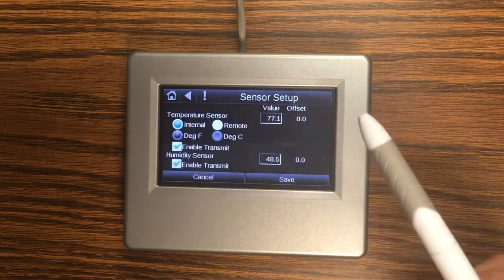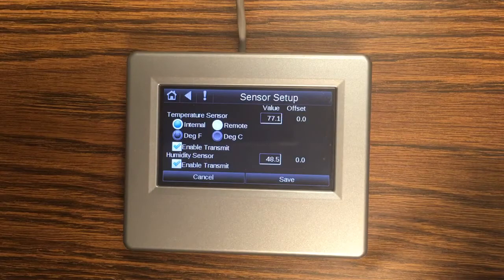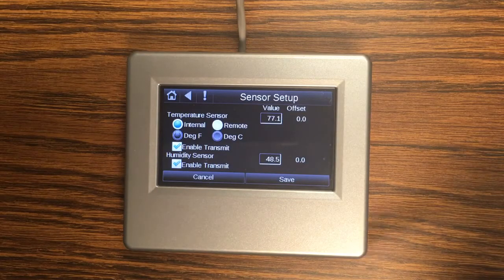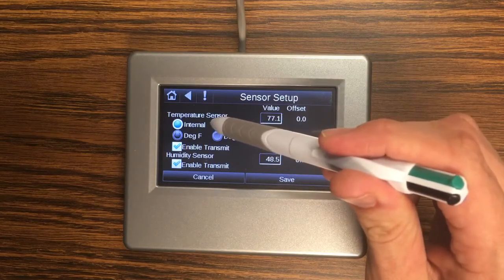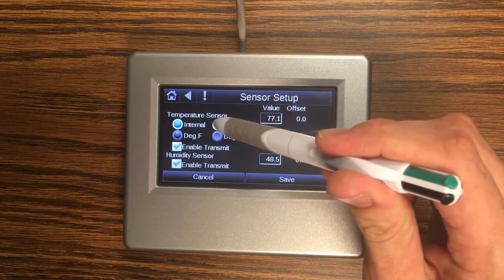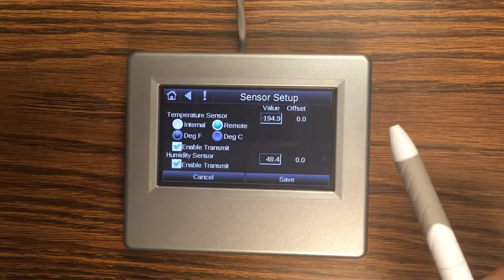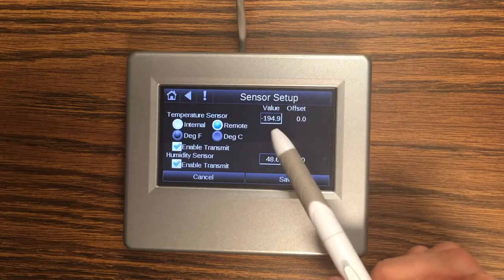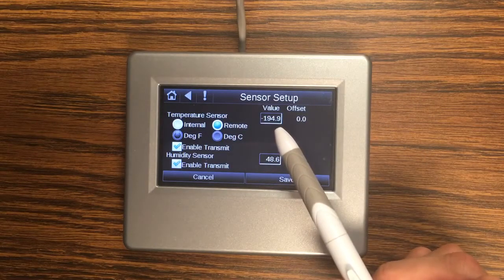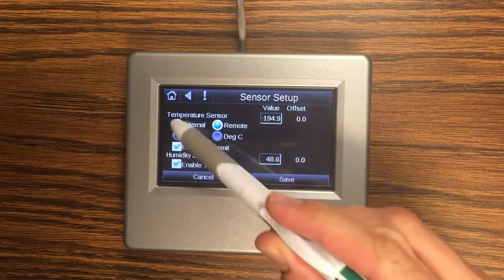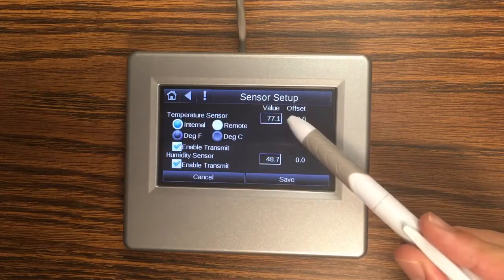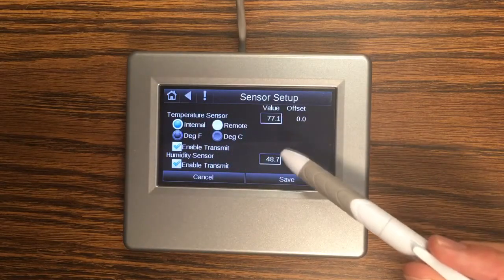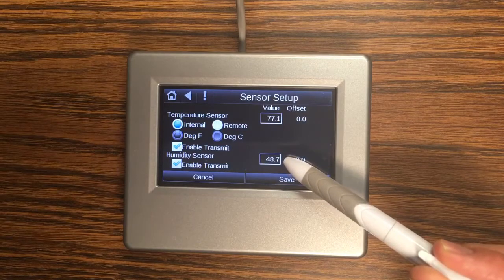Sensor setup is where we pick between the internal sensor for the touch screen and that remote thermistor that I showed you on the backplane. So if I switch to remote you can see I get an open circuit value for the thermistor. And if I switch back to the internal I'm reading a 77 degree 48% relative room.